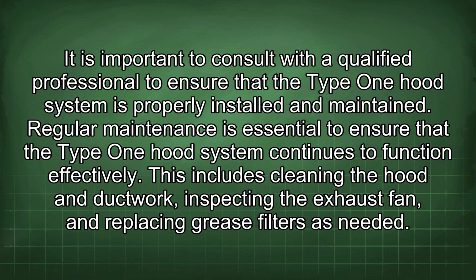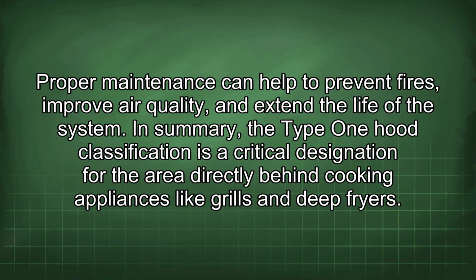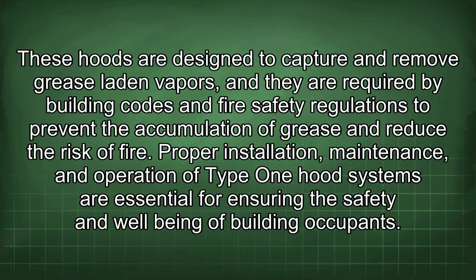This includes cleaning the hood and ductwork, inspecting the exhaust fan, and replacing grease filters as needed. Proper maintenance can help to prevent fires, improve air quality, and extend the life of the system. In summary, the Type 1 hood classification is a critical designation for the area directly behind cooking appliances like grills and deep fryers. These hoods are designed to capture and remove grease-laden vapors, and they are required by building codes and fire safety regulations to prevent the accumulation of grease and reduce the risk of fire.